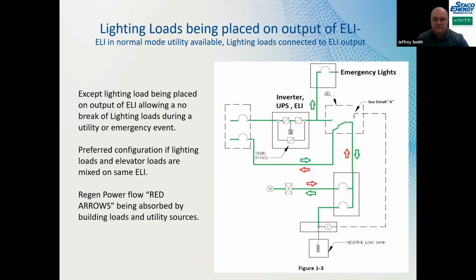We're on emergency power right now. So the UPS, emergency lighting inverter, is now feeding the load, and it goes down and feeds the system. The red arrow shows this is where the regenerative power is coming back, flowing back into the resistive load bank. We have over 60 units out there right now that utilize this. We are just starting to put out systems now that run for 2 hours, because that requirement just came this January for California.